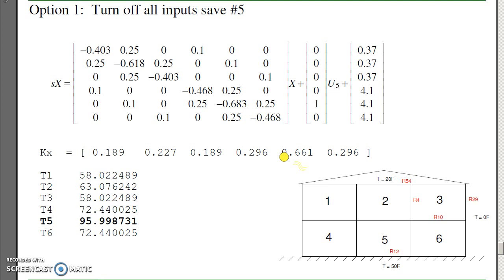Suppose I only use the heater in apartment number 5, right here. In that case, this becomes my B matrix. I can use LQR methods to find the feedback gains. And here, Q is just the identity matrix. I care about all six apartments. Find the feedback gain. Now find the DC gain from the disturbance to the states, with my setpoint being 70 degrees. And I wind up with the following temperatures. Note that apartment 5 is extremely hot. That's where my heater is. All the other ones are much colder. So that's one option you can have. If I have six heaters, just turn five of them off. That doesn't work real well in this case, because I wind up with one apartment blistering hot. The other ones are cold.